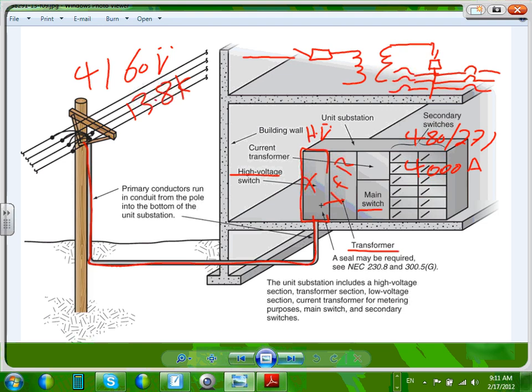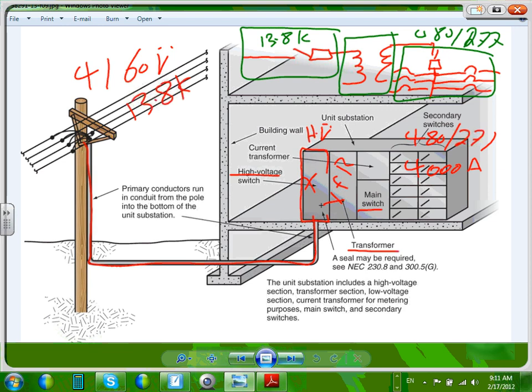Does it make sense? That's what the riser looks for, the substation. And in a case like this, you're going to have a 13.8 kV. This will be a 480/277. And this is one section, two sections, three sections. You can do it this way in three sections, or you can build them all together in one big box. They call it unit substation.